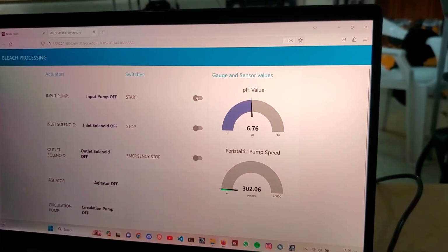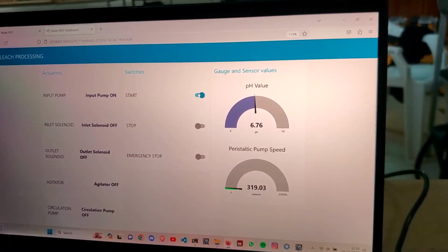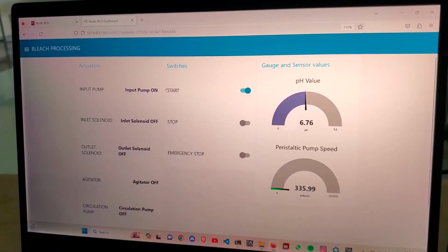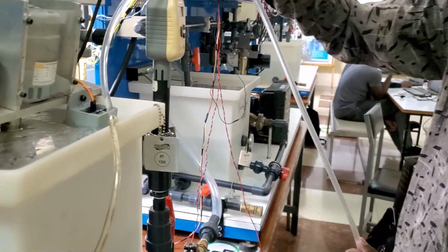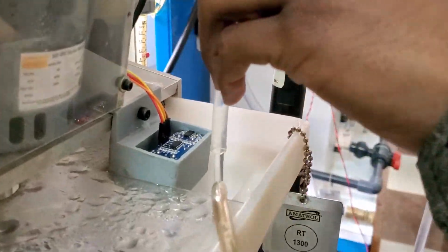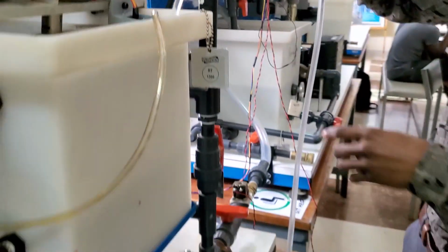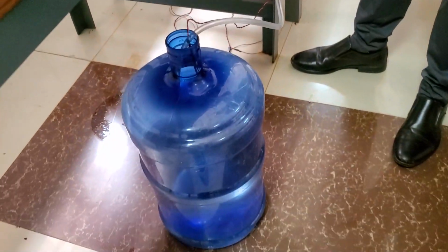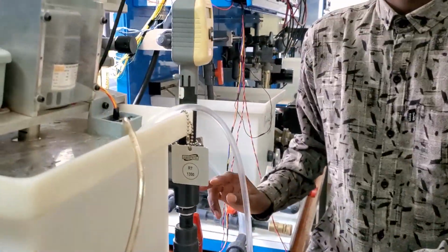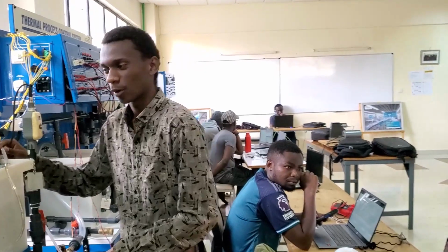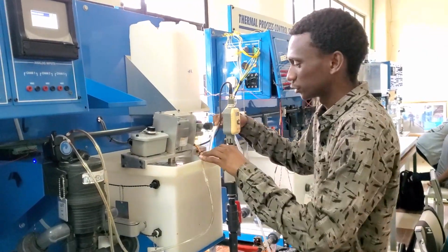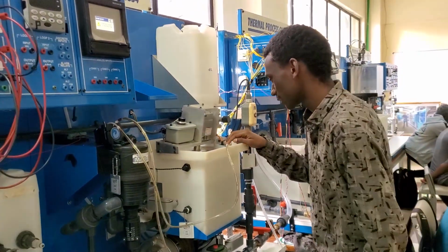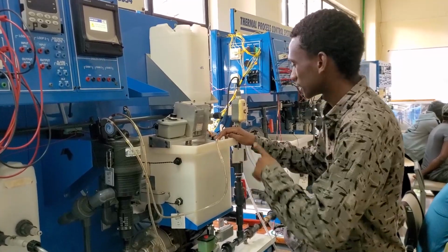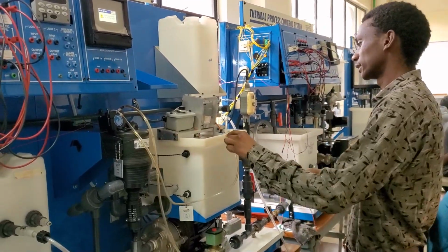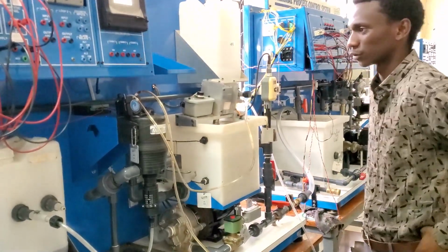Here, one can start the input, and the process starts with the input pump on. As you can see, first the liquid water used for diluting the hypochlorite solution is pumped into the reactor tank. Once the pump has pumped in the required amount, we have an ultrasonic sensor that will be used to monitor the level and start the sequence and the regulation of the pH control.